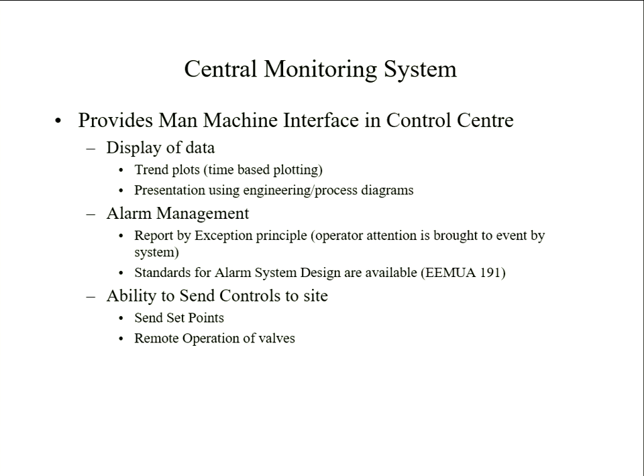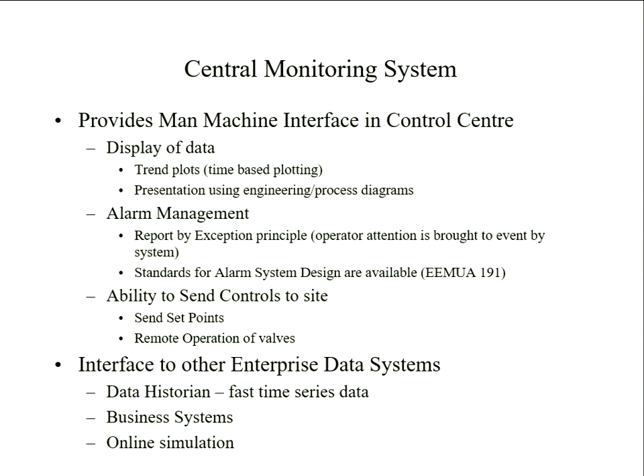This is not a national grid site, so just this sort of display. You get different styles, and again, people prefer different colours, and every time a new system comes in, people look at what's the best way of presenting data to the operator. But that single loop flow controller, the most recent control system that's been put in to the Gas National Control Centre, they made the interface on the SCADA system look very much like that flow controller. Previously it had all sorts of data shoveled in boxes, and as sites change, you were finding you were getting pipes running over your data boxes, and your displays become, if you're not careful, confusing. You need to be simple to the operator.